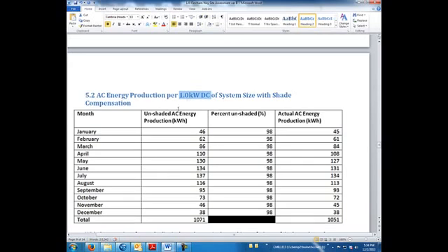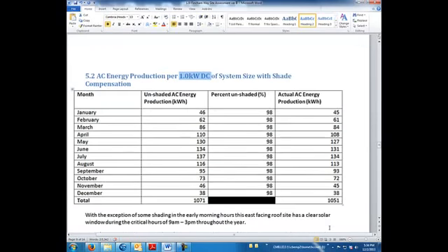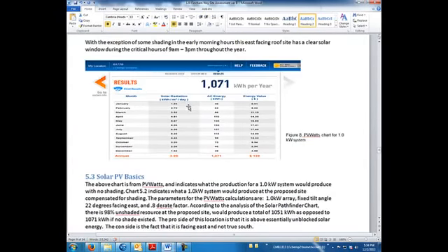So this is what 1K will give me of energy performance: about 1,000 kilowatt hours of electrical energy at the end of this 1 year of production. That just gives you a rough ballpark to know at this location, this site, this is what you have to have. To really complete this site assessment properly, you really must have a 1 kilowatt system and a PVWatts showing where this data came from.